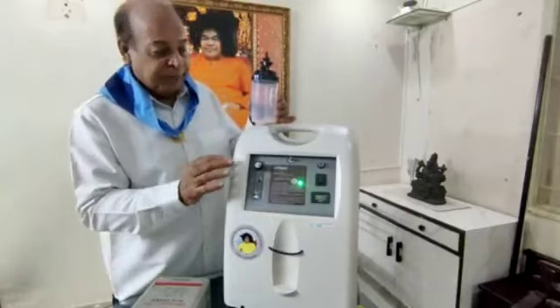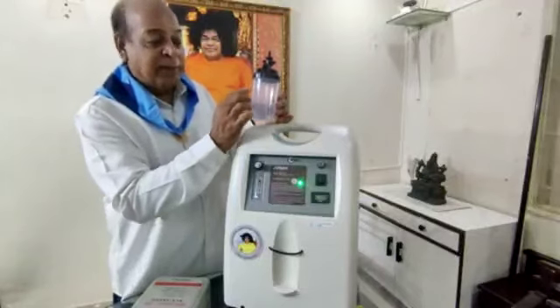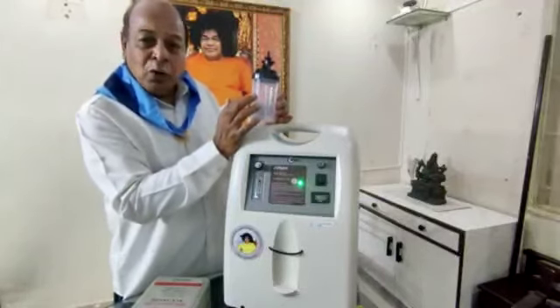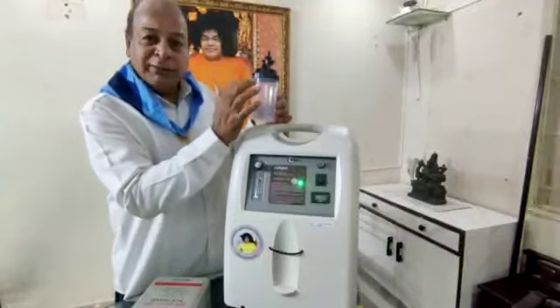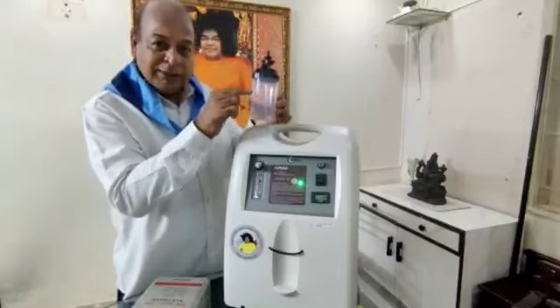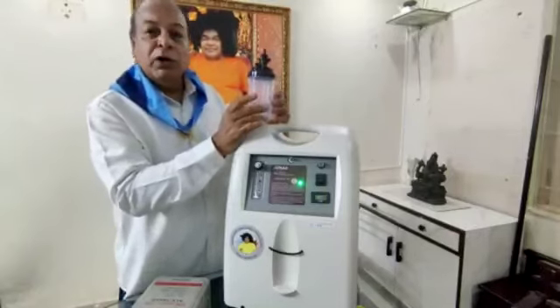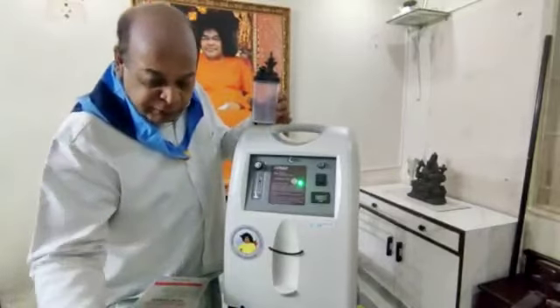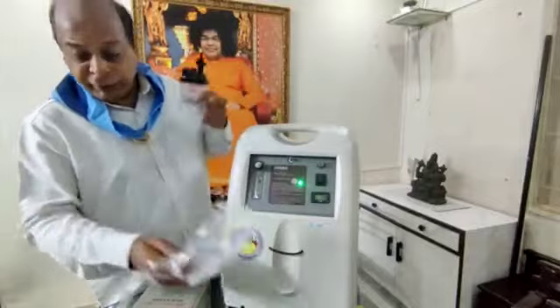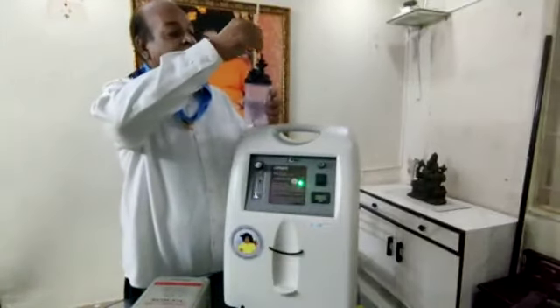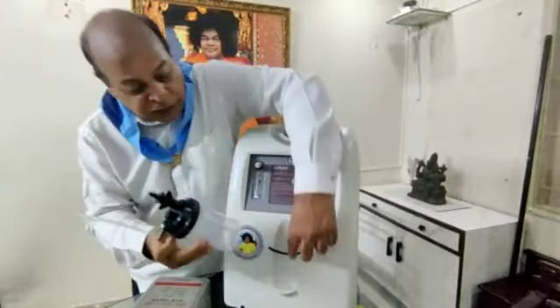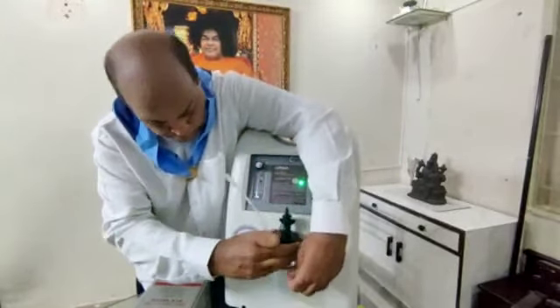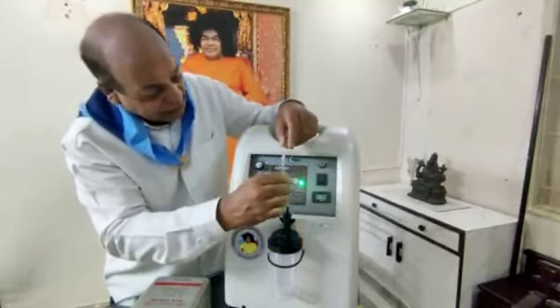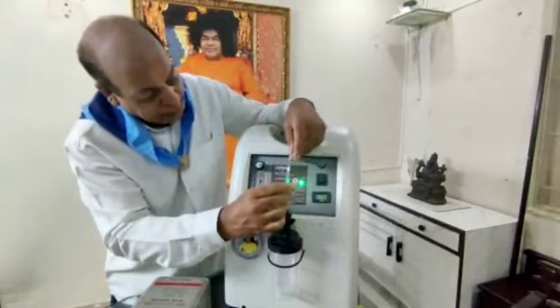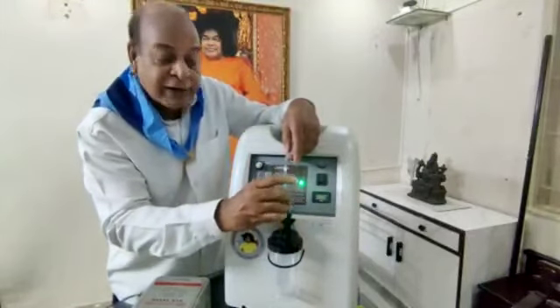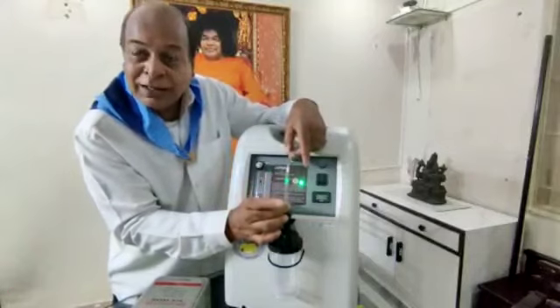Avoid using mineral water. Now these have got 2 marks here, minimum and maximum. Fill up the water till below the maximum level. Don't fill it over the maximum level. It should be lower than the maximum line over here. Once you fill it up, this bottle is ready for use. Then you have a pipe which also comes with this humidifier bottle. You fix this in here, and this goes over here. After you fill the water, you put it here, it sits very easily. Then this gets connected like this. I am not doing it right now because I don't want to plug it in. This is a one-time plug-in in most concentrators. So this goes like this and this is ready for use.